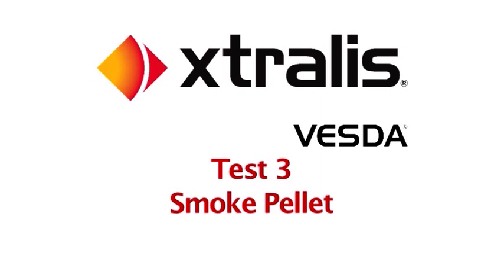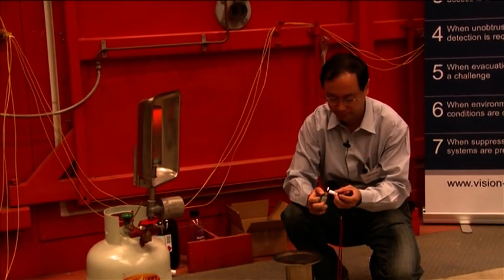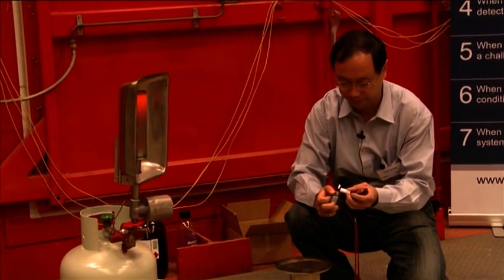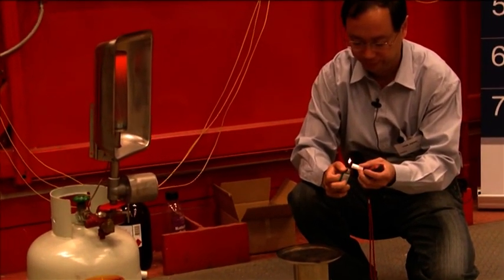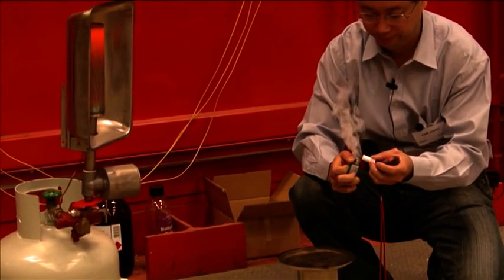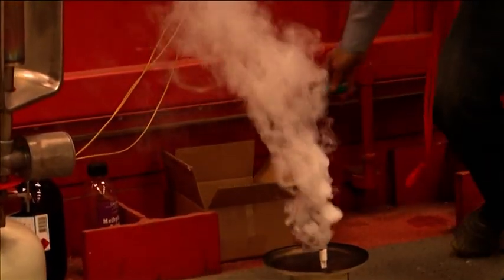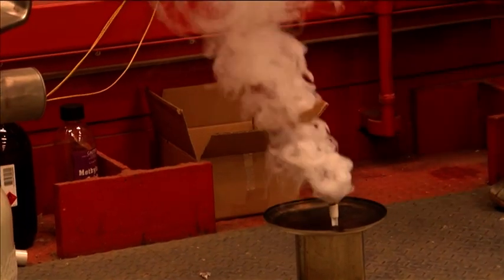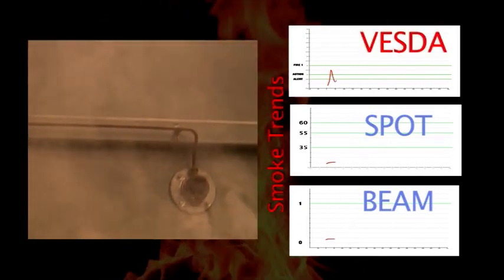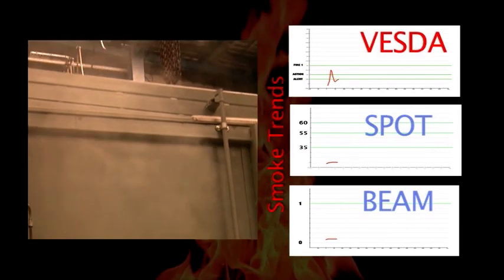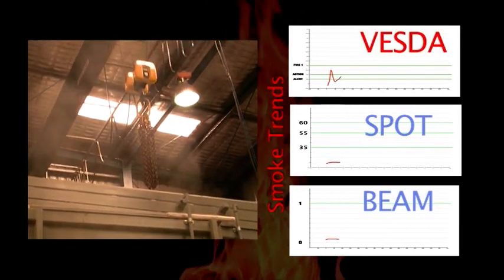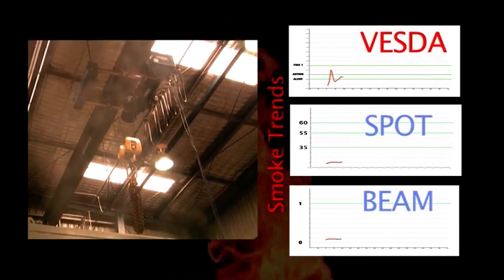Smoke pellet. Test number three is conducted to AS standards and consists of a small three-gram smoke pellet, assisted by a radiant heater to provide a constant heat release rate. Here, the VESDA unit went into alert after just seventy-two seconds and fire one after ninety seconds. Both the spot detector and beam detector failed to react within the eight-minute period.